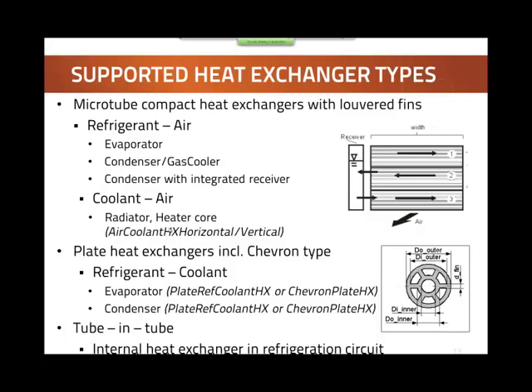Another important type is plate heat exchangers, including the chevron type. They are also used for refrigerant-coolant applications — for example, if you want to use the refrigeration cycle for battery cooling, you may want to go to a secondary fluid, and then you need a heat exchanger that transfers heat from this fluid to the refrigerant. A rather simple type is the tube-in-tube heat exchanger, also included.